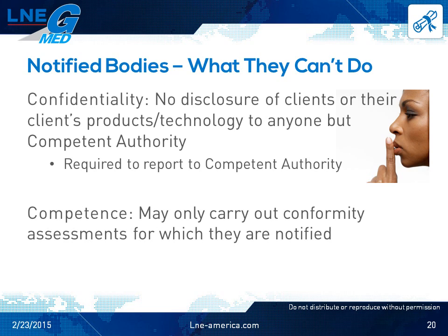Notified bodies also have a duty of competence, meaning that when a notified body is notified to a specific directive and conformity assessment, it has to maintain its competence by having the right people on staff, making sure they are trained properly, having the right equipment, etc. This also means that notified bodies can't carry out conformity assessments for which they aren't notified. Like I said before, a notified body that is only notified for, say, construction products can't perform conformity assessments for medical devices.